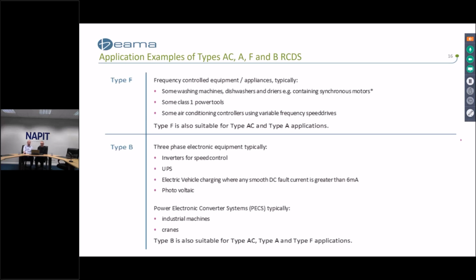So here we've got some examples of the Type F and Type B RCDs. We envisage that some modern appliances, which include, for instance, synchronous motors, may require protection with a Type F RCD. Type F RCDs are also suitable for Type AC and Type A applications. So as you can see on the slide, frequency controlled equipment, some washing machines, dishwashers and dryers containing synchronous motors, some Class 1 power tools, and some air conditioning controllers using variable frequency speed drives. And once again, Type F is also suitable for all of the Type AC and Type A applications.